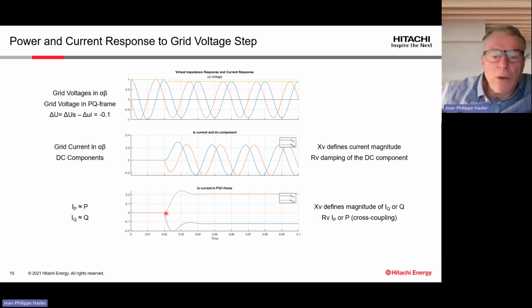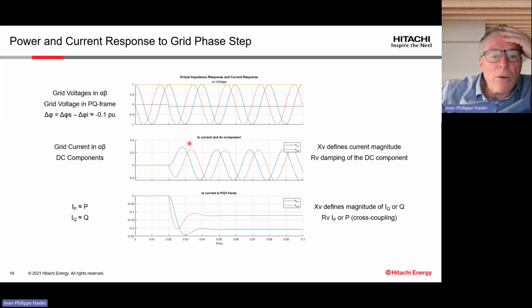The oscillation you see in the power, which has a frequency of about 50 Hertz, is not really an oscillation, but what you observe when you have a DC component. So this overshoot only says that we have a DC component in the power or reactive power. I will not talk about the step in the phase angle, but it has a very similar response, with no delay.